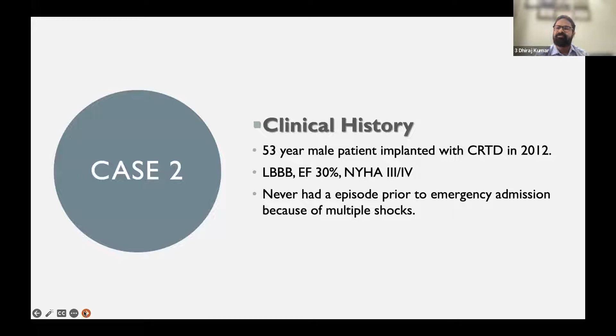There's another case, a 53-year-old male patient implanted with CRT-D, ejection fraction of 30%, never had any episode. 2 years down the line, he presented to you with multiple shocks. Now you see this EGM, and you can easily recognize that in the ventricular channel, something abnormal is happening. So A sense, V sense, A sense, V sense, and then you see multiple high frequency signals, often more than one per cycle length. If you remember, more than one per cycle length, high frequency signals, only there in ventricular channel, they are nothing but lead abnormality, lead related noise, and that noise has been classified as VFib, and a shock has been delivered.